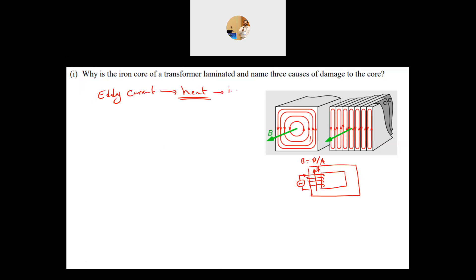We call these eddy current losses. Laminating the core means that instead of one bulk cross-section, the area is made up of stacked laminated sheets that are electrically insulated from each other. This confines the eddy currents to circulate only within each individual sheet. Since the sheets are very thin — as small as 0.5 millimeter — the eddy currents are significantly reduced, which is the purpose of lamination.